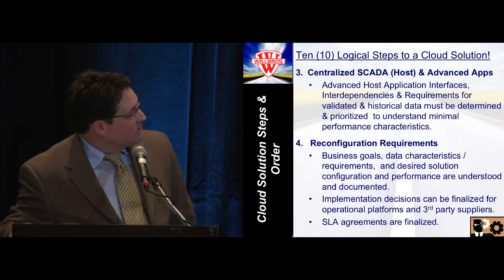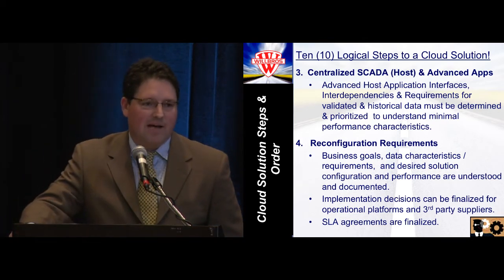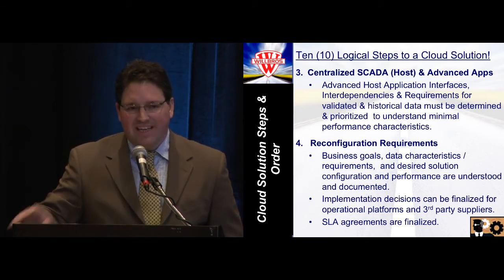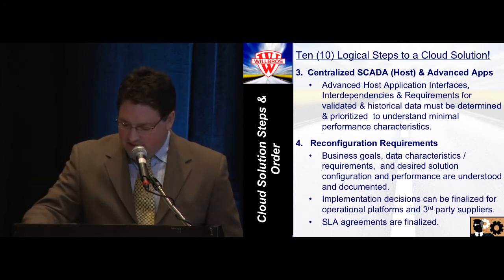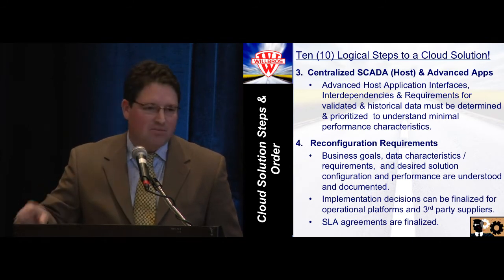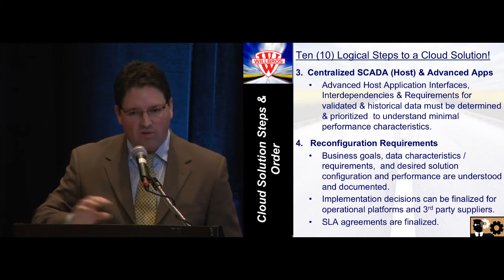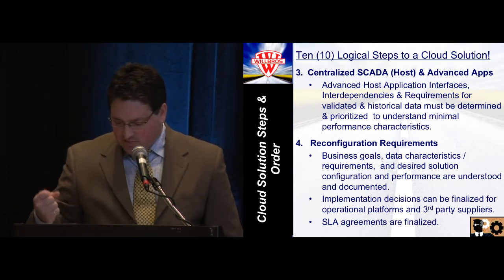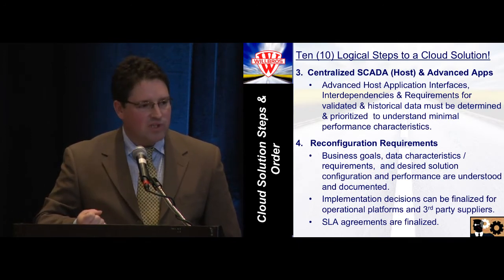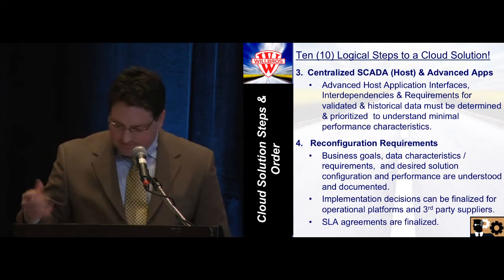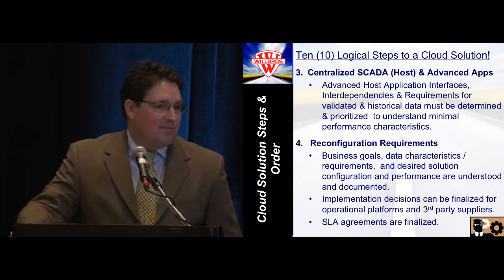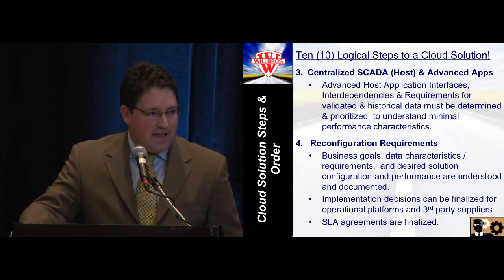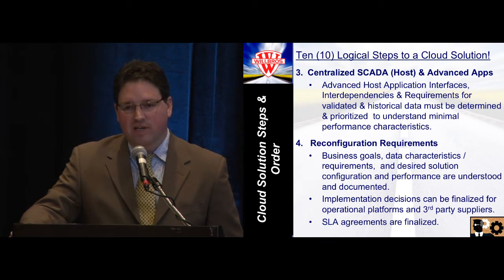Step three was evaluating the centralized SCADA host and advanced applications. The SCADA host was the polling engine bringing everything into the cloud-based solution. We evaluated the advanced application interfaces, the interdependencies, and all the validated and historical data to set minimal performance characteristics for the overall system. Step four was the reconfiguration requirements — examining business goals, data requirements, and desired solution configuration and performance at each step in the chain. At this point, we finalized all operating platforms, third-party vendor software, and set up initial service level agreements with the cloud providers.